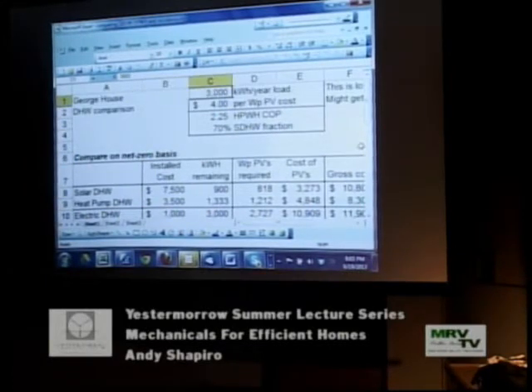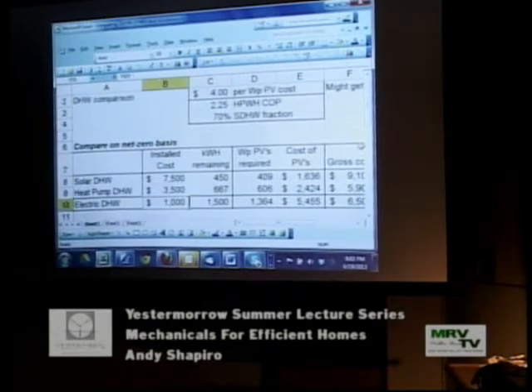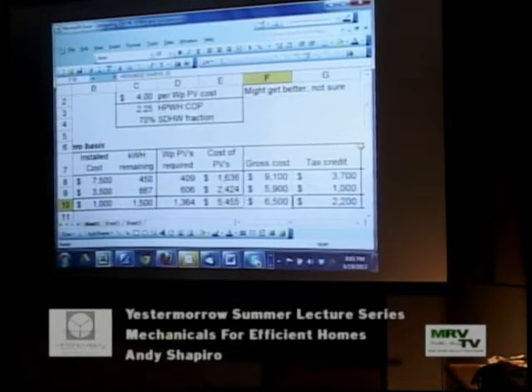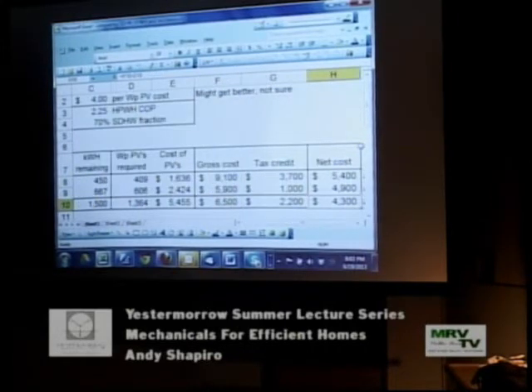So let's pick a really low load here, 1,500 kilowatt hours a year. The installed cost for the electric water heater is only $1,000—this is a good electric water heater, like a Marathon, very well insulated. But your PV cost is higher, so your gross cost is $6,500. You get some tax credit on the PV, so the lowest net cost in this case is the resistance water heater with the PVs at a very low load, because PV costs have come down so far. This whole thing has turned itself on its head in the past 5 years.